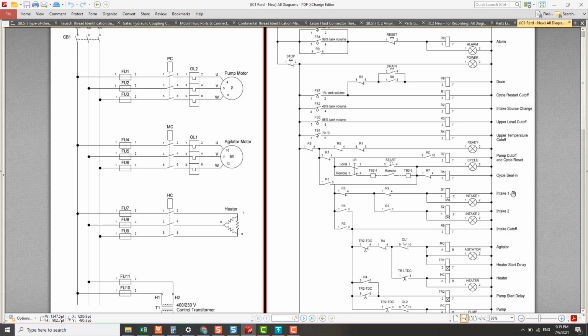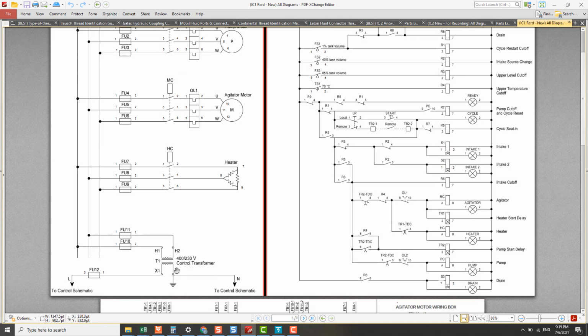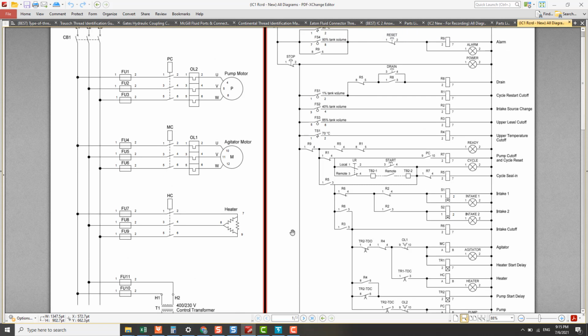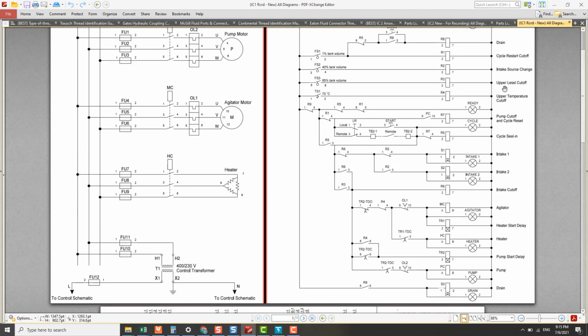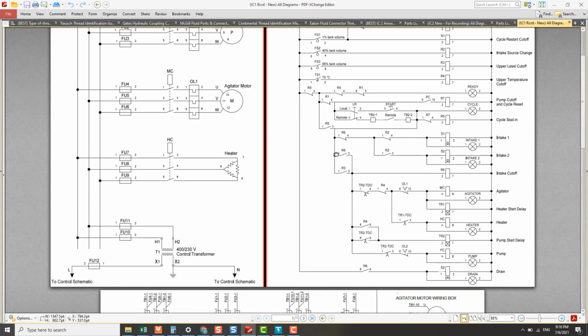So usually this kind of strange thing happens because the transformer is faulty and giving a low voltage, or there is a loose connection at the common neutral line. Loose connection can be very loose or slightly loose. A very loose connection can be treated like an open circuit. A slightly loose connection can be treated like a load with slightly high resistance. So most likely it is due to a slightly loose connection. Anyway, we have to check both.